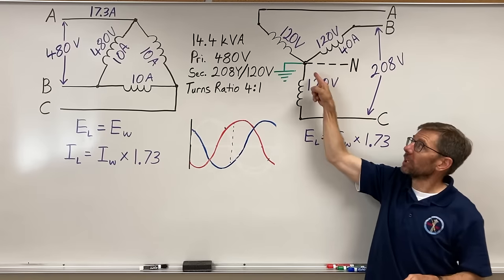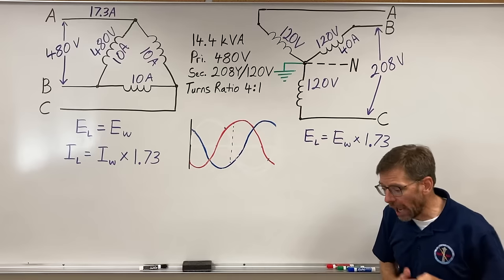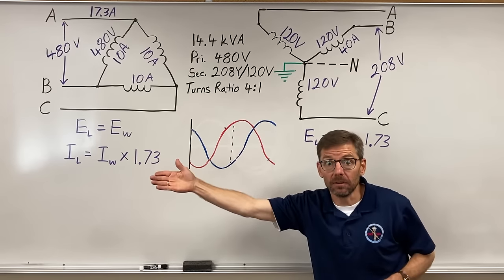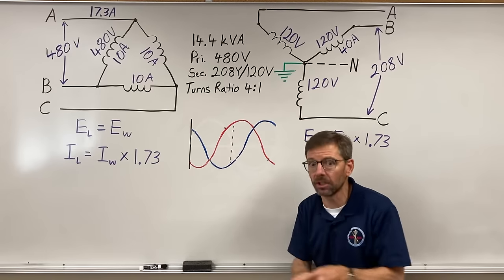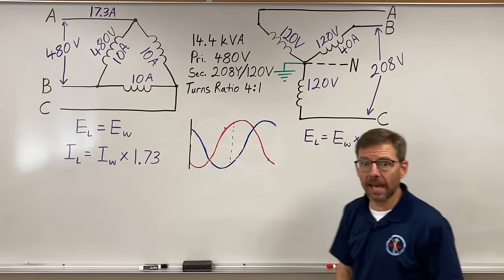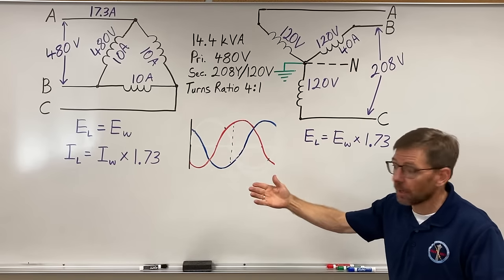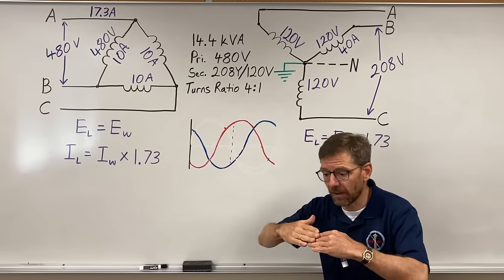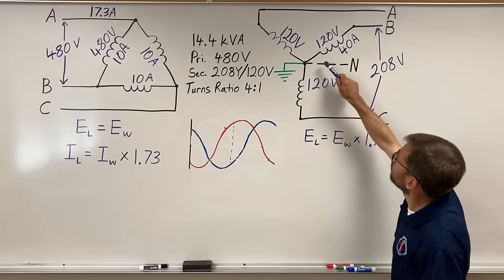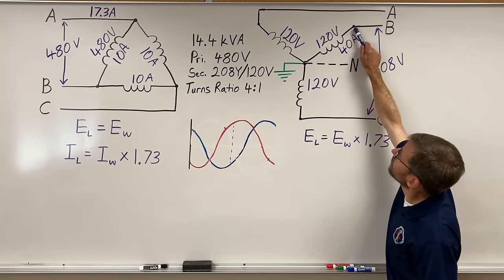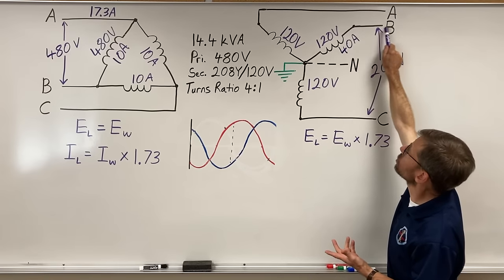Well, if there's 40 amps on each phase, let's look at this. It goes back to Kirchhoff's law. Whatever amps go into a certain spot, got to leave. They can't just hang out and send some of them on. The bus is moving. They're all on the bus. They're all going, all the amps, as long as I got a circuit closed. If I have an open circuit, all the amps stop. So 40 amps go through here. They come to this point. And in a Y, that side of the winding just goes straight down the line. All 40 got to go.